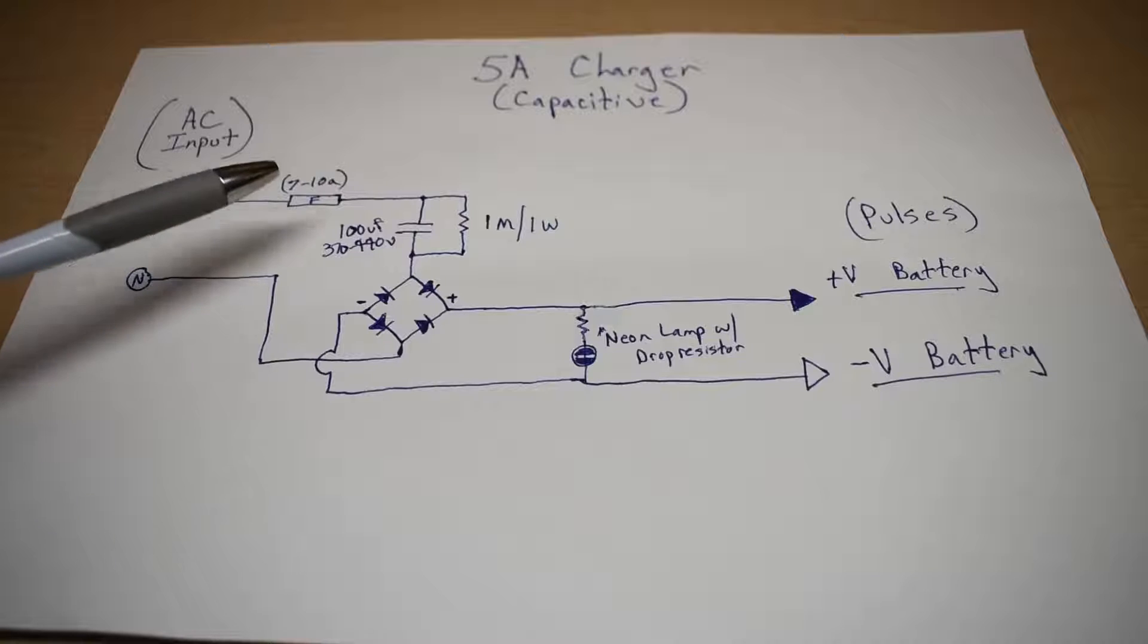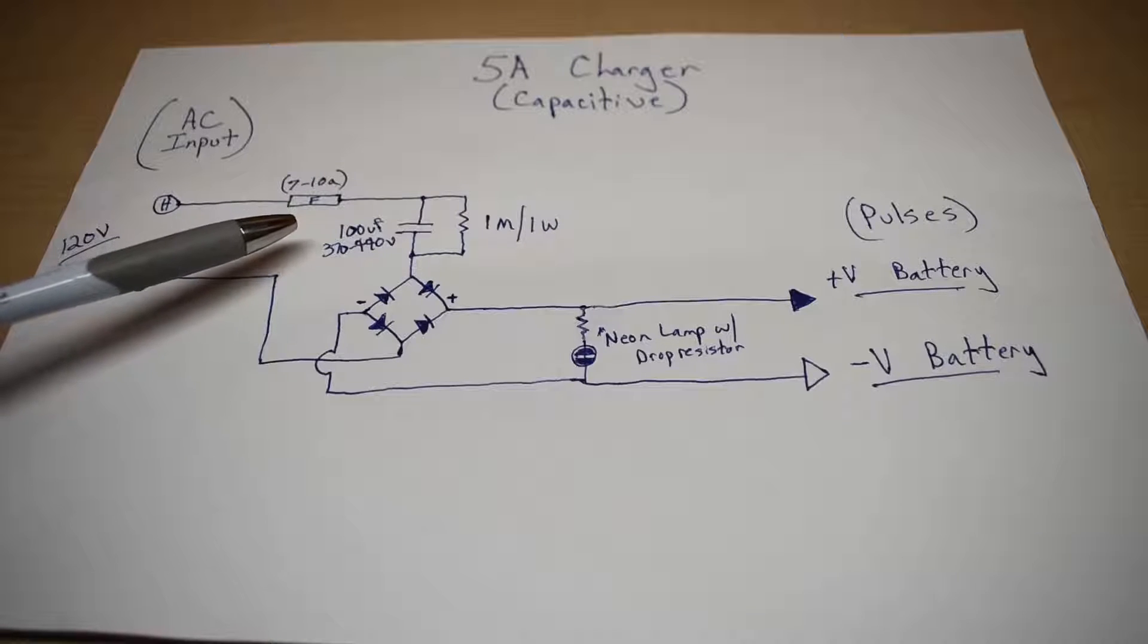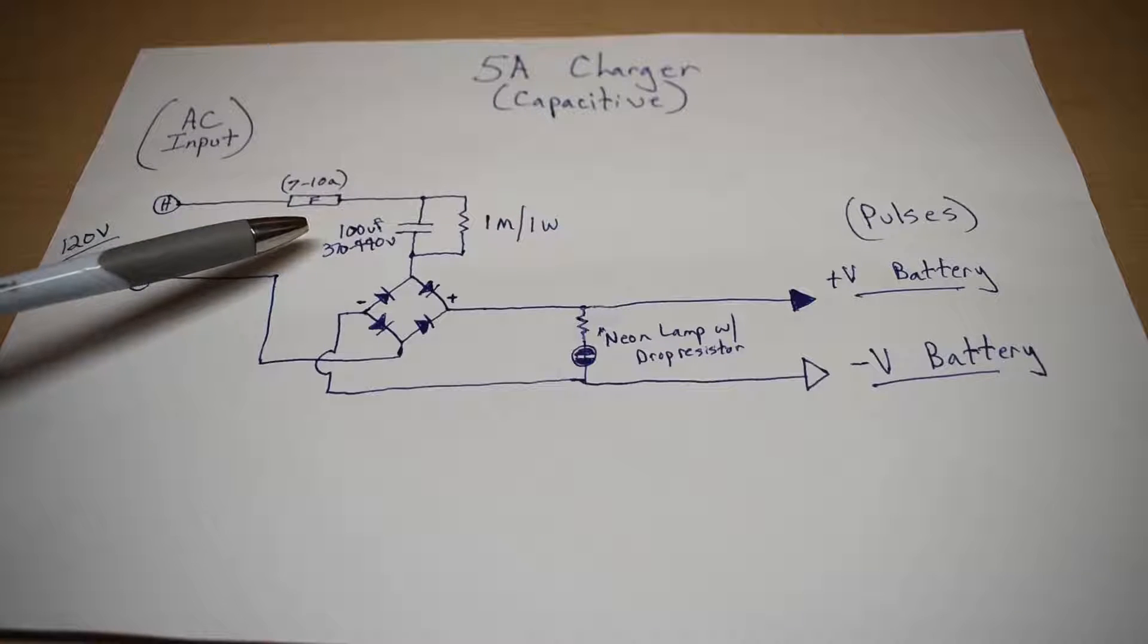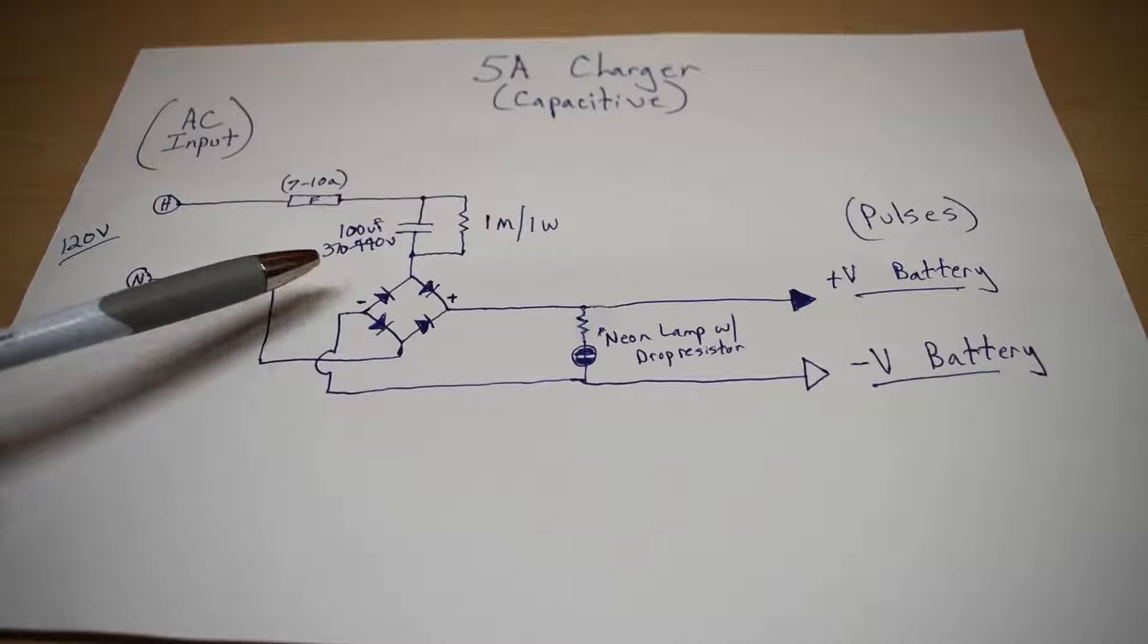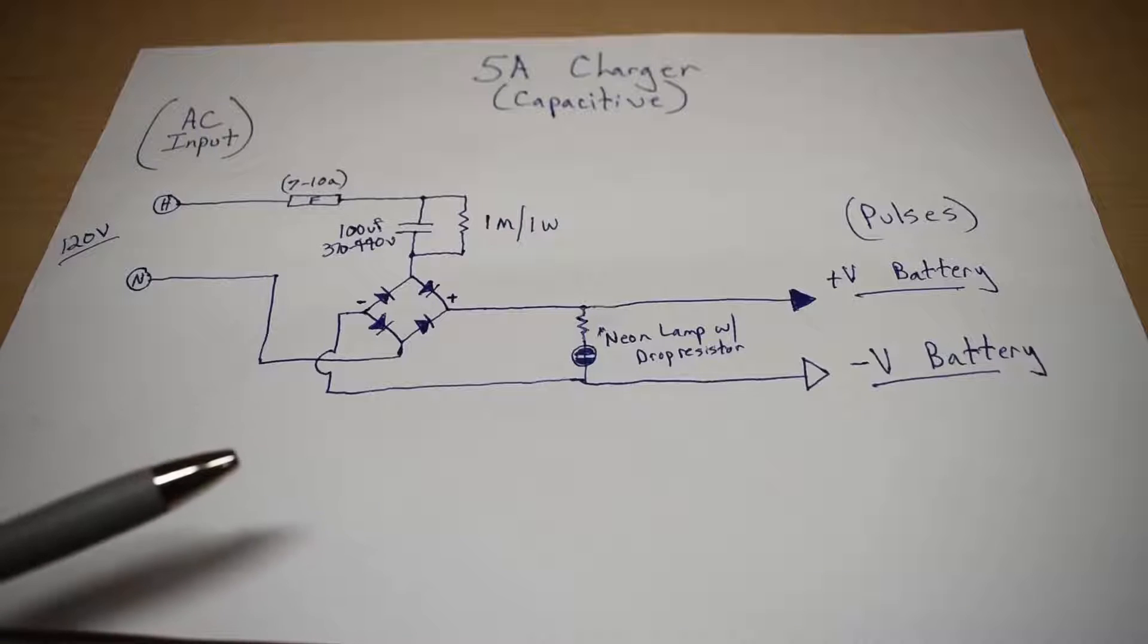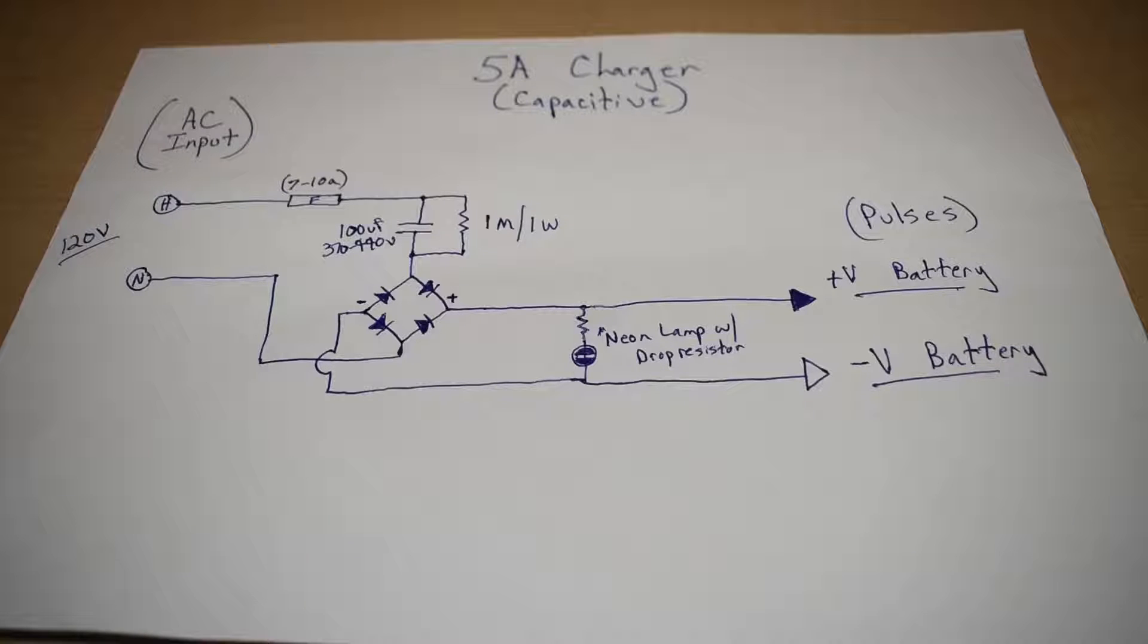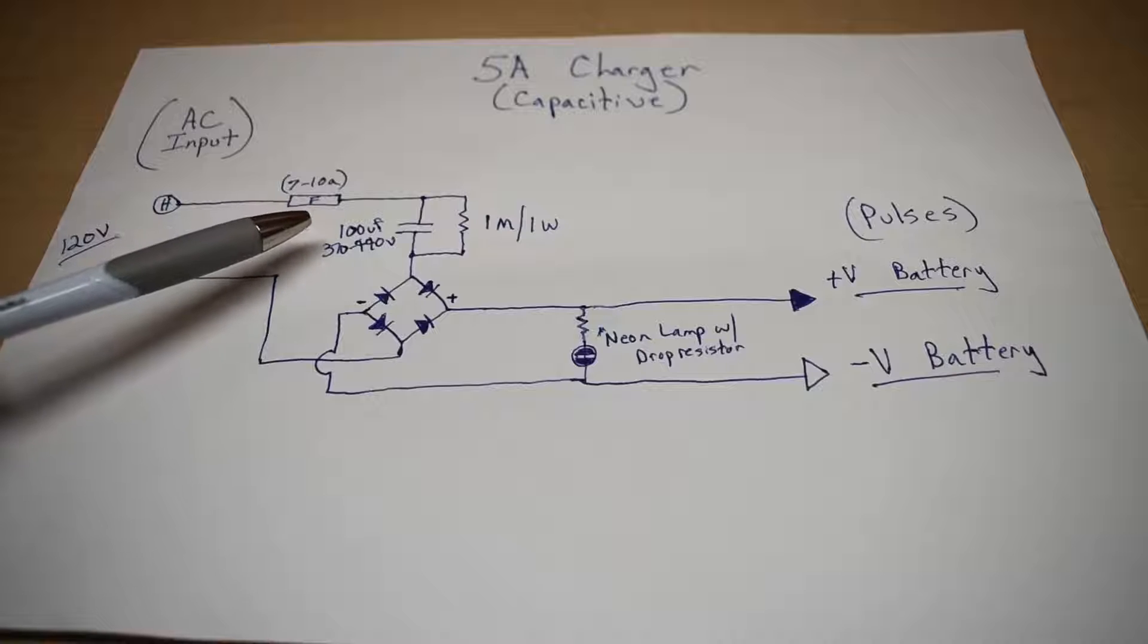The reason why we use an oil-filled run capacitor is because we want to be able to restrict the flow of current without generating heat like a resistor. So a 100 microfarad capacitor at 60 Hz has a resistance that would be equivalent to a 25 ohm resistor. These capacitors are usually in a 370 to 440 volt range, and you must use a run capacitor that is oil-filled. Do not use one of these capacitors here, it's a start capacitor. It will explode if continuous current is applied. The oil-filled capacitors are designed to be left in circuit.